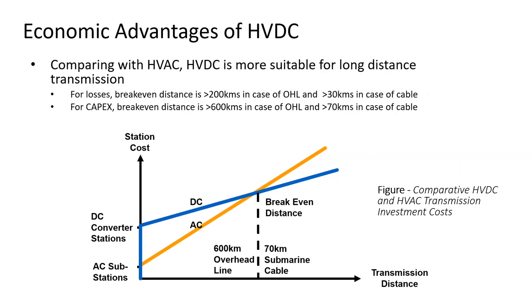So this picture shows the transmission distance, which is the distance between the sending end converter and the receiving end converter station. If the transmission distance for an overhead line type HVDC system is 600 kilometers or more, then HVDC is cheaper than HVAC. Whereas if the distance for a cable type HVDC system is 70 kilometers or more, then HVDC is cheaper than HVAC. Please note that what I'm sharing today about the break-even point, for overhead line HVDC and cable type HVDC systems, is typical information or data.